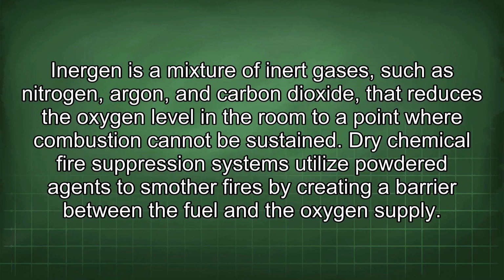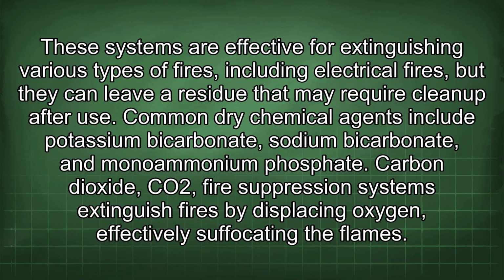Inergen is a mixture of inert gases such as nitrogen, argon, and carbon dioxide that reduces the oxygen level in the room to a point where combustion cannot be sustained. Dry chemical fire suppression systems utilize powdered agents to smother fires by creating a barrier between the fuel and the oxygen supply. These systems are effective for extinguishing various types of fires, including electrical fires, but they can leave a residue that may require cleanup after use. Common dry chemical agents include potassium bicarbonate, sodium bicarbonate, and monoammonium phosphate.